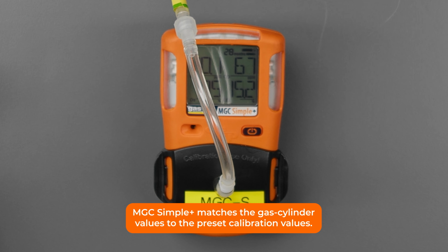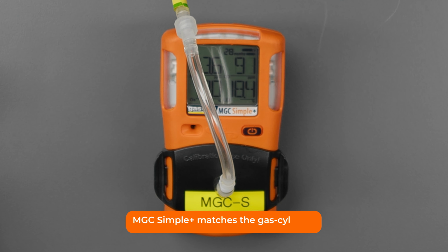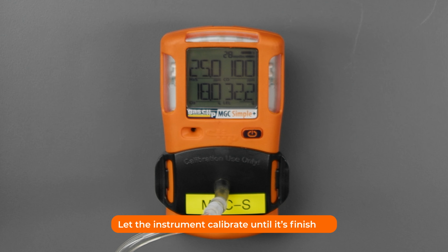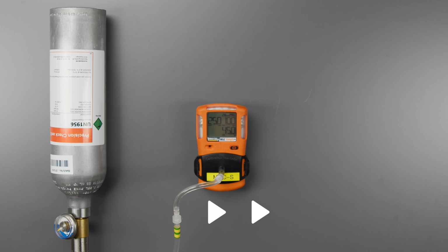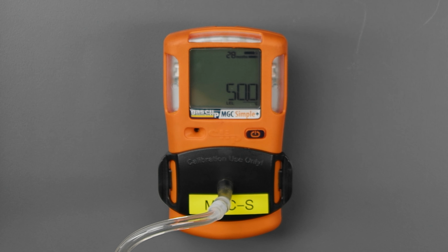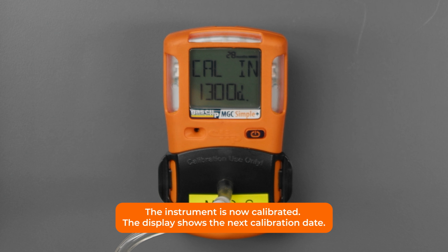MGC Simple Plus matches the gas cylinder values to the preset calibration values. Let the instrument calibrate until it's finished. The instrument is now calibrated. The display shows the next calibration date.